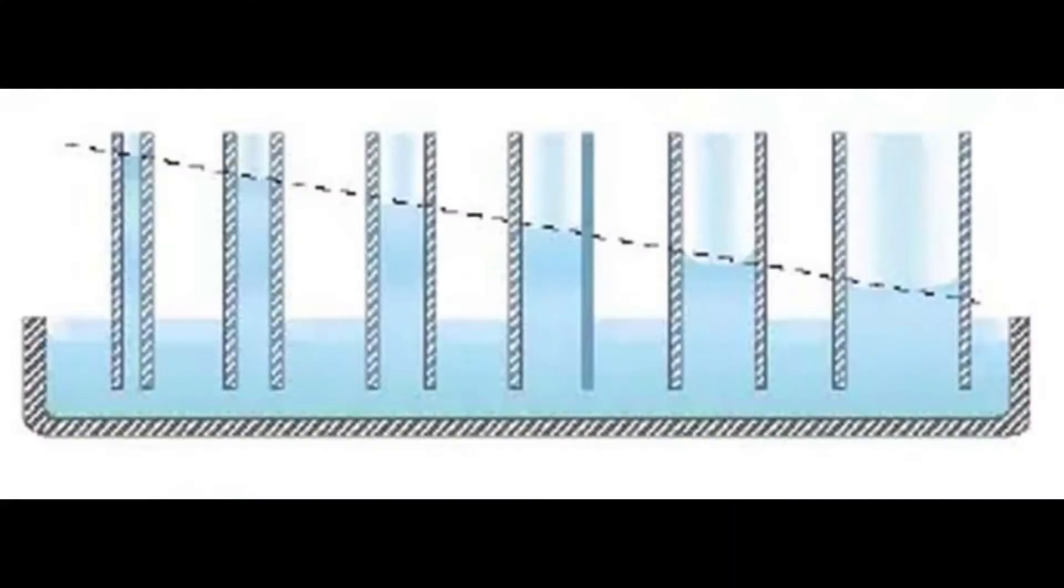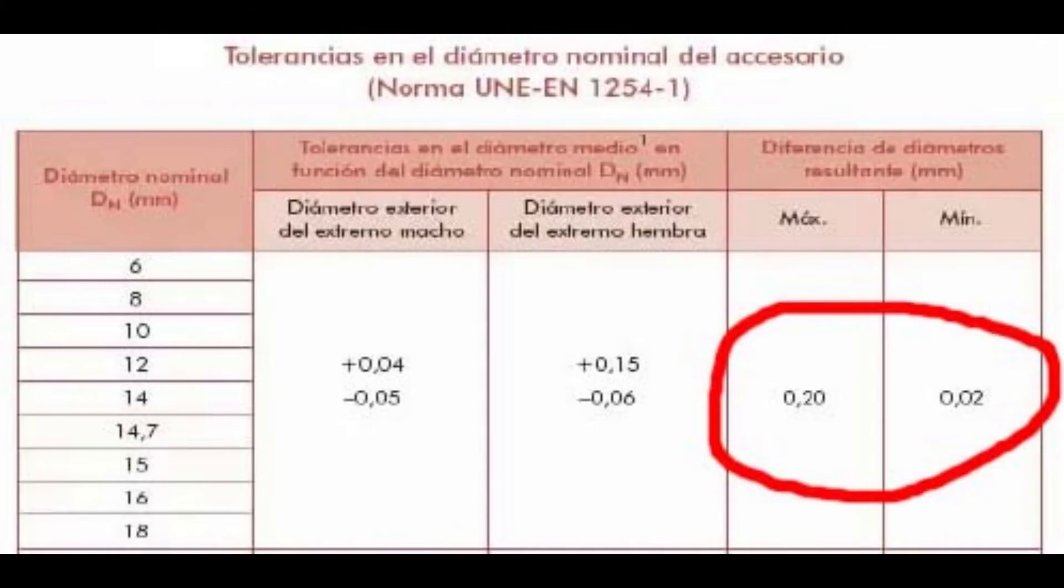However careful we may be, and even if the tool has an alignment bit, swaging can produce crooked fittings. For soft solder and hard solder to flow well by capillarity between the walls of the pipe and the fitting, that space must be very uniform, quite precise. And the tolerance allowed is very small.